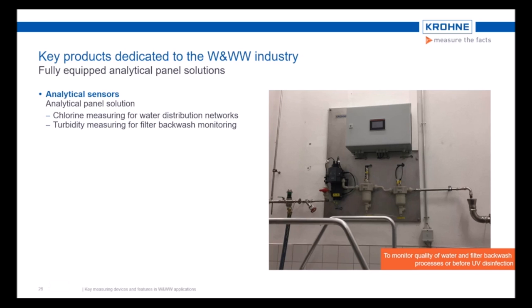Often such turbidity solutions are also used before UV disinfection modules to guarantee the appropriate quality of water, which is required to make a UV module effective. Such solution boards are tailor-made and can be freely equipped with the required sensor or materials. In this case, the customer combined the turbidity with an ORP and a conductivity sensor, both, by the way, in a SMARTPAT version without the need of an external transmitter.